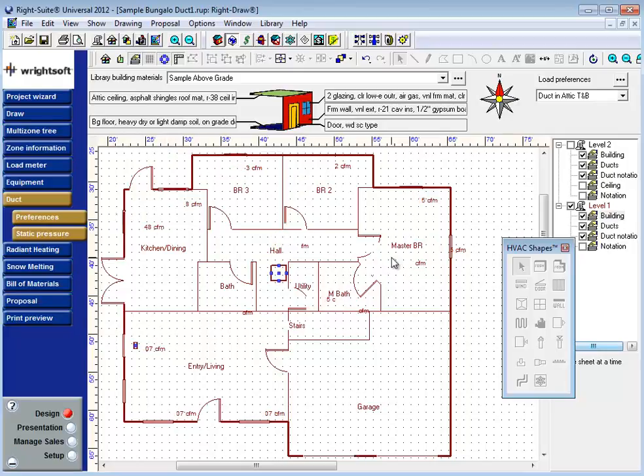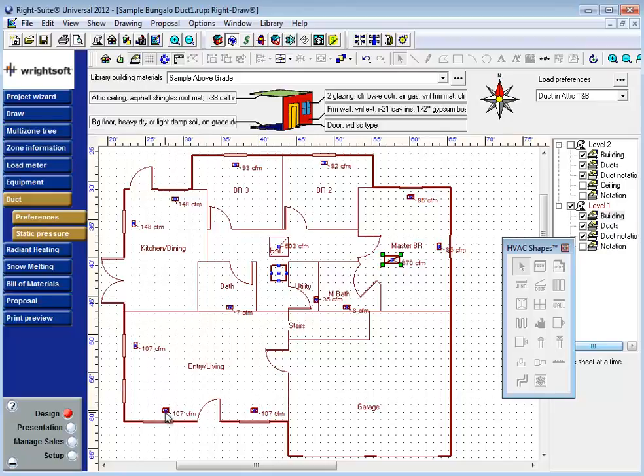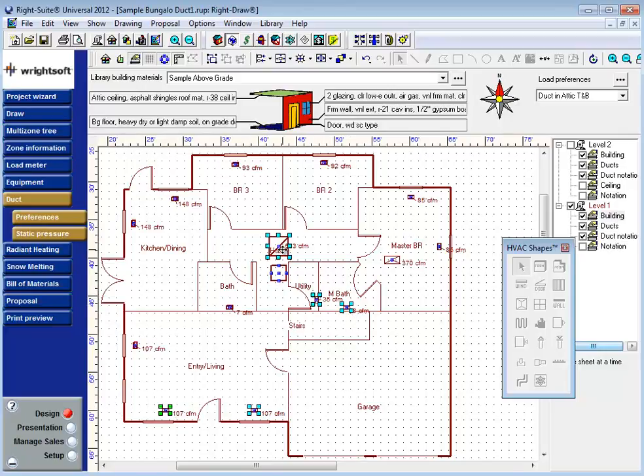To reassign them, simply select the supply grills that you want to reassign. You can use the shift key, you can draw a box around them with the pointer, group them together, and along with those supply grills, select one return that you'd like to assign them to. It is very important you only select one return. You cannot split this air across several returns yet.